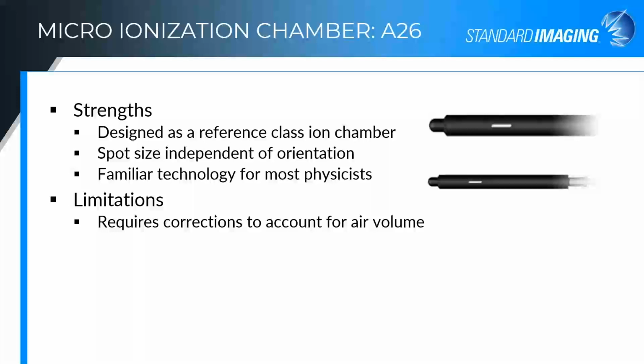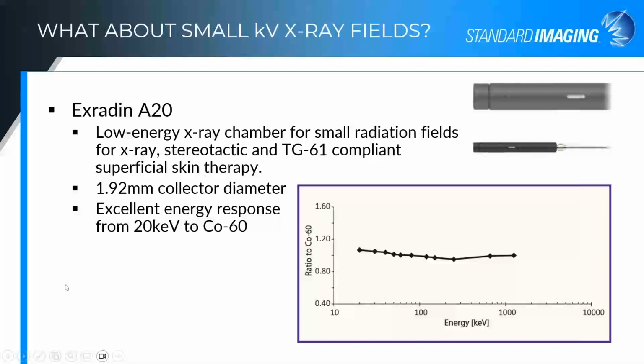Limitations of ion chambers, all ion chambers, especially in small fields, is that they require a correction to account for the low density of the air volume in the field. So that was megavoltage beams.